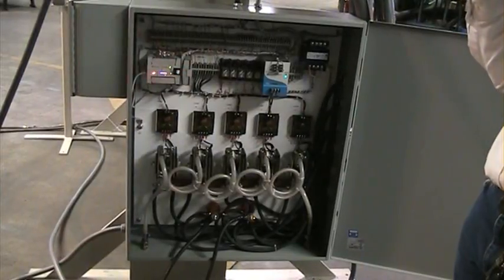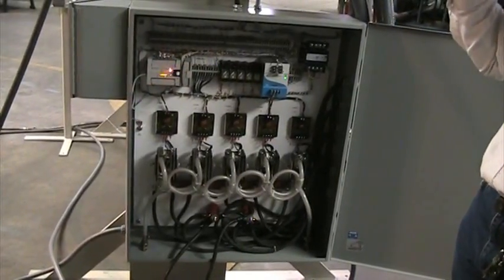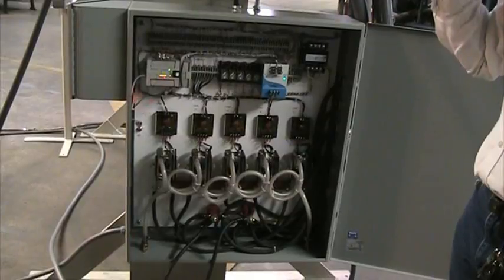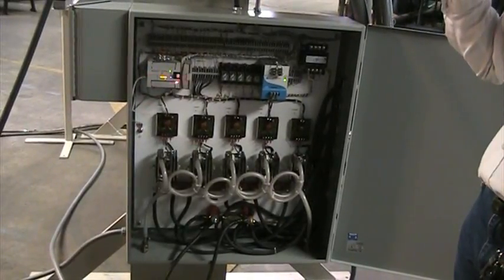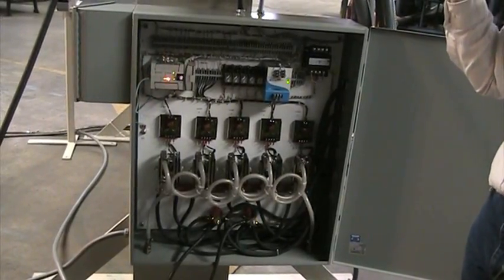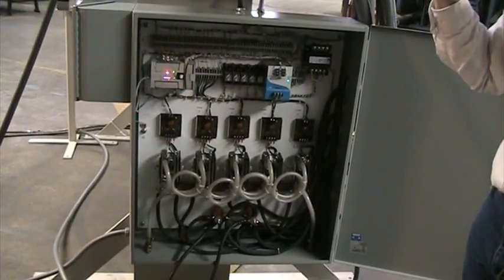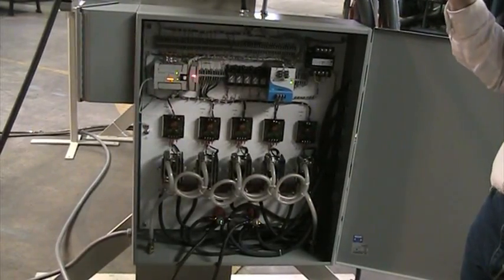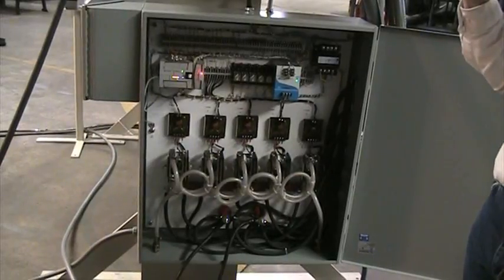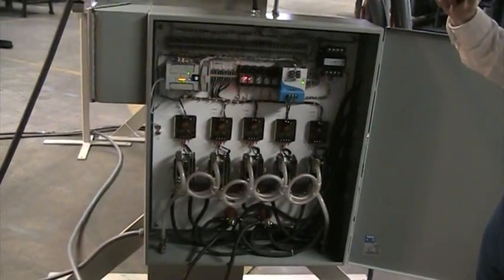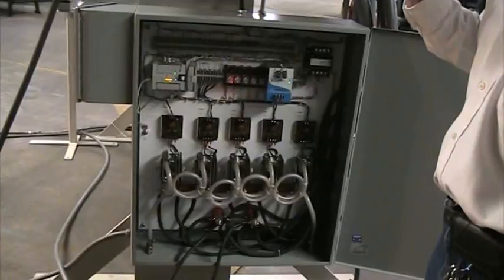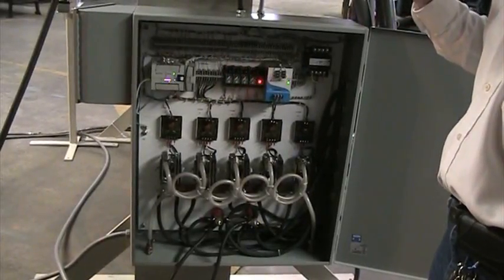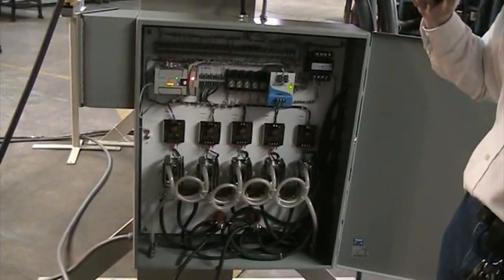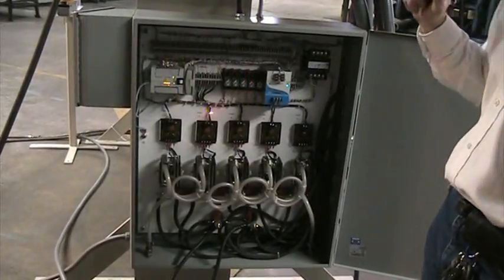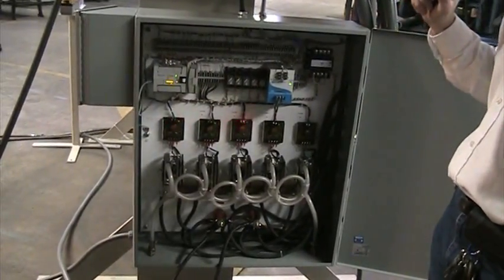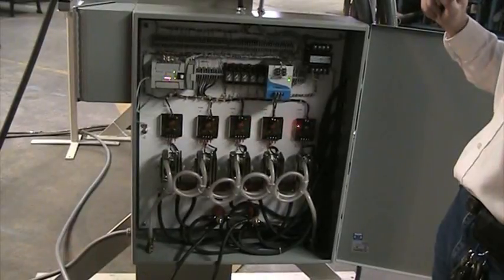Okay, currently just going from left to right, you've got your PLC control. This cable, as it comes out of the PLC, goes to the HMI, which again is the human machine interface. That's where you're going to be entering your information. You've got a Micrologix 1200 and then a daughter card, which is a 16 output DC relay card. You've got the dry contact relays. They're 24 volt coils that are taking the signal from the PLC to actually allow the signal to go to the appropriate firing card. That's these 5 cards here on the bottom.